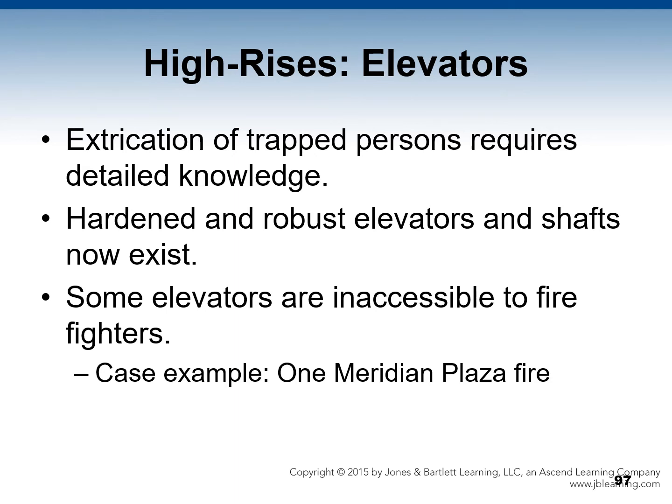So I do encourage you again to look this fire up and read everything about it. You will learn an awful lot. Again, we're going to hear in terms of elevators reference the One Meridian Plaza fire. In this fire, all power for lights and elevators failed. In total darkness, all equipment had to be hauled up 20 or more floors.